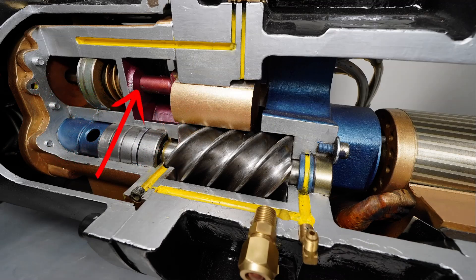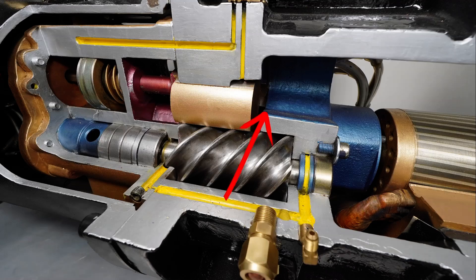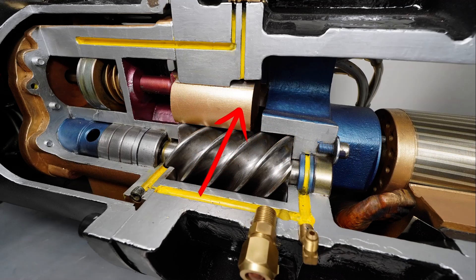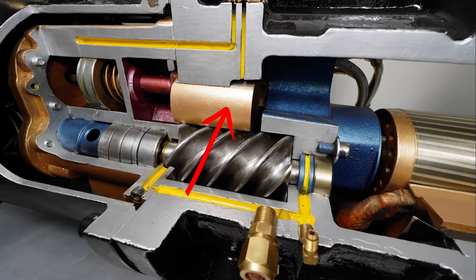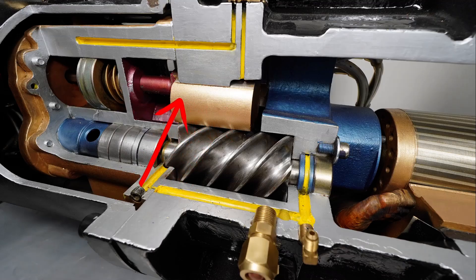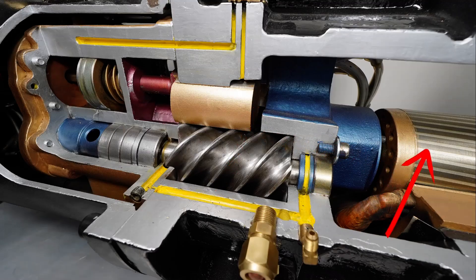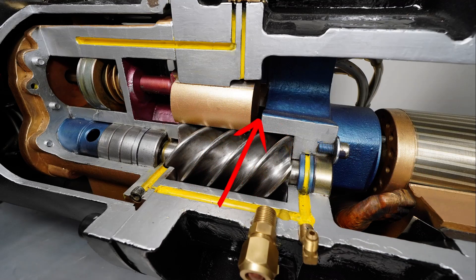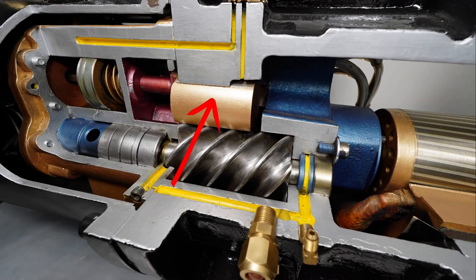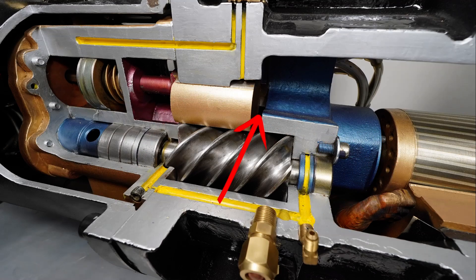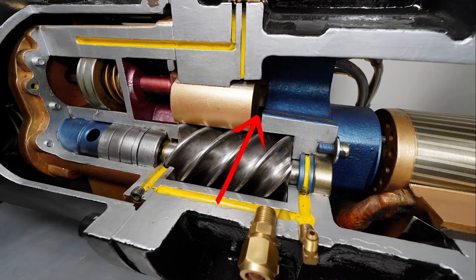Either way, this motor will start off at a minimum state and the slide will start off at a fully unloaded state. So in this case, it'd be slid all the way to the left. Before we start increasing speed on the motor, we will push the slide to a fully loaded position. So when you have a combination between these two, just understand this is the process. And then this is how I've seen it done across the board. This isn't specific to a particular manufacturer, but we're going to push that slide to a fully loaded state first. Then once the slide is that fully loaded, we will start to increase our motor speed. And essentially this just becomes another way of reducing capacity on the motor and on the compressor because on their own, they can only unload to a certain point, but put in combination together, they can unload even further. I'm just pausing there to kind of let that sink in for a minute.